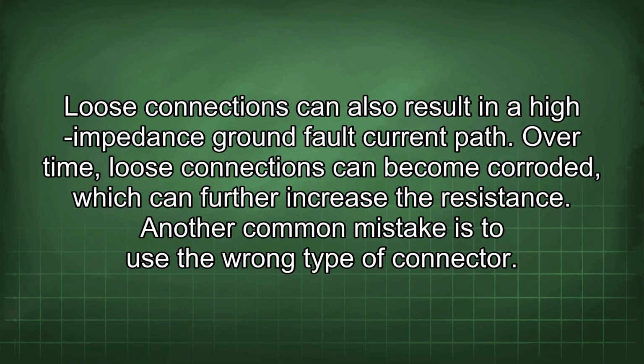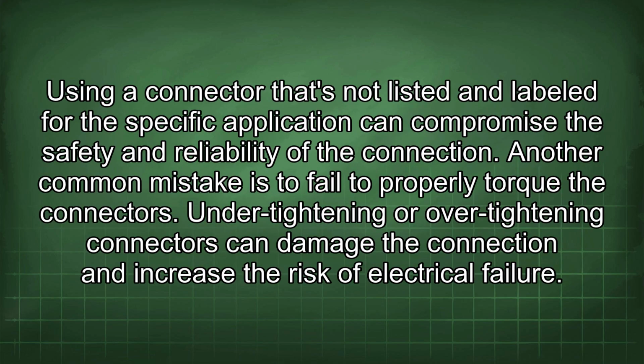Another common mistake is to use the wrong type of connector. Using a connector that's not listed and labeled for the specific application can compromise the safety and reliability of the connection. Another common mistake is to fail to properly torque the connectors. Under-tightening or over-tightening connectors can damage the connection and increase the risk of electrical failure.